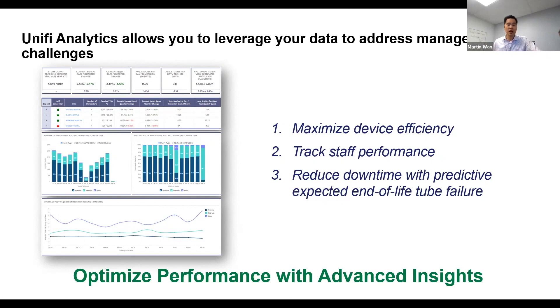The last piece is reduced downtime with predictive expected end-of-life tube failure — something Hologic is really excited about. It's our foray into more proactive monitoring and replacing of component parts. Specifically on the gantry, we're able to predict the end-of-life of a tube failure. The analogy is your cell phone battery — when it says it's going to zero, it's the exact same thing from a tube-life perspective. With all three data points — maximizing device efficiency, tracking staff performance, and reducing downtime — you'll be able to optimize your workflow.